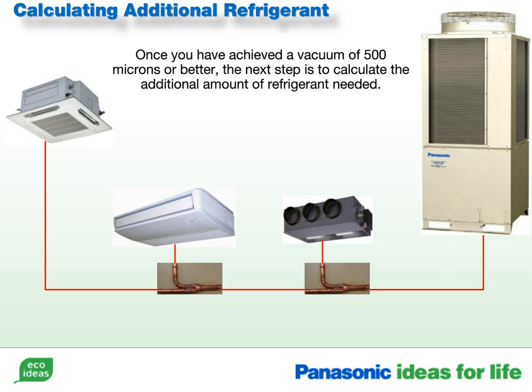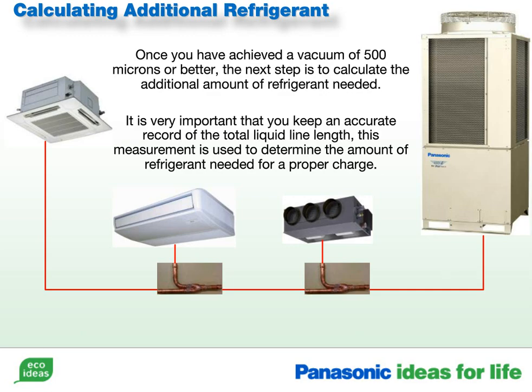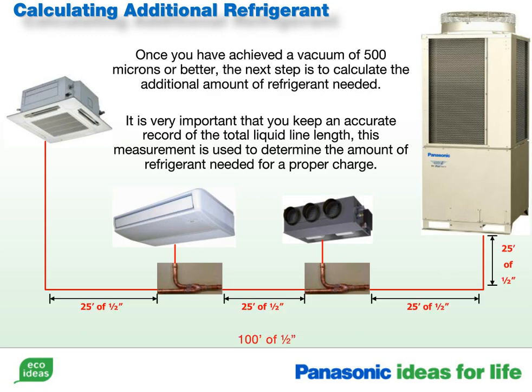Once you have achieved a vacuum of 500 microns or better, the next step is to calculate the additional amount of refrigerant needed to properly charge the system. During the installation process you should keep an accurate count of the total liquid line length. You do not need to include distribution joints and elbows in your total liquid line length. In this example, we have a total of 100 feet of half-inch, 100 feet of 3/8, and 100 feet of quarter-inch. Now you will need to multiply the total length of each line size by the multiplier.